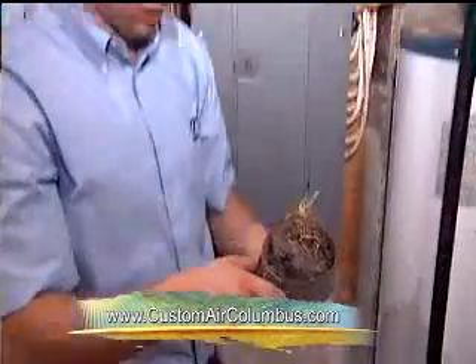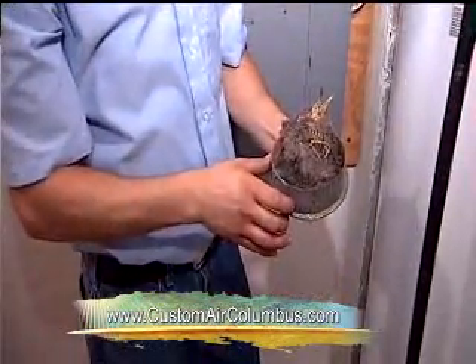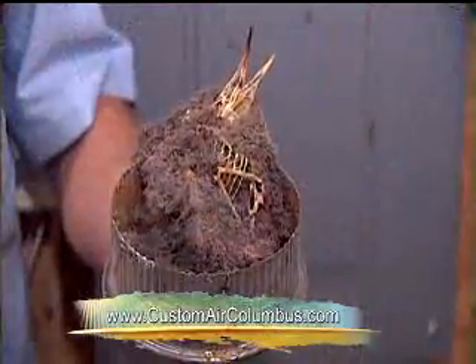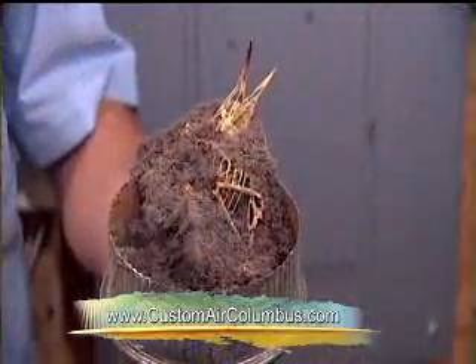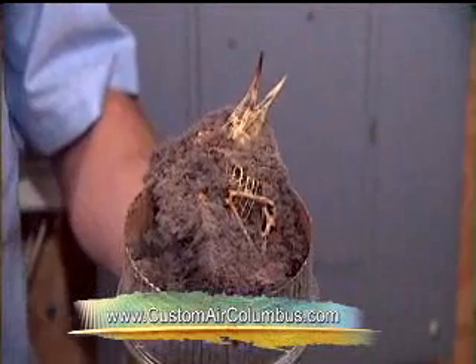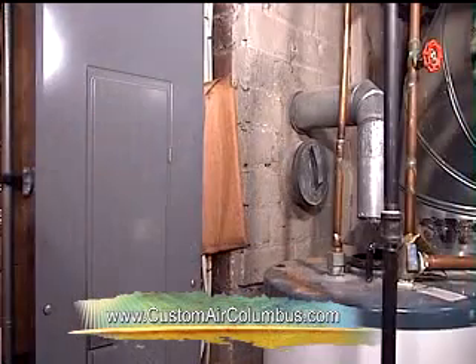Yeah, there's the dead bird, a little skeleton. We pulled that out a couple weeks ago, and it had been there a while. So what does that do to someone's unit? They didn't even know it was there. The unfortunate part is the furnace would come on and try to vent up the chimney, but there's a blockage, so the chimney gases come out into the house because there's nowhere else for it to go. That's where you see carbon monoxide.